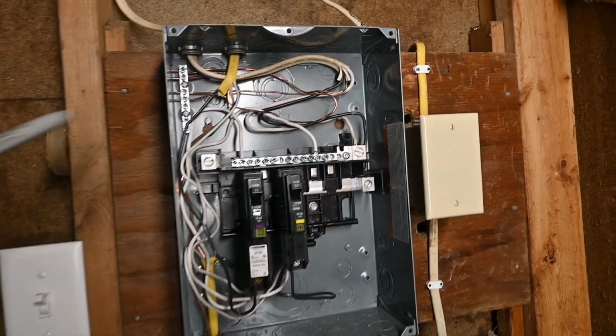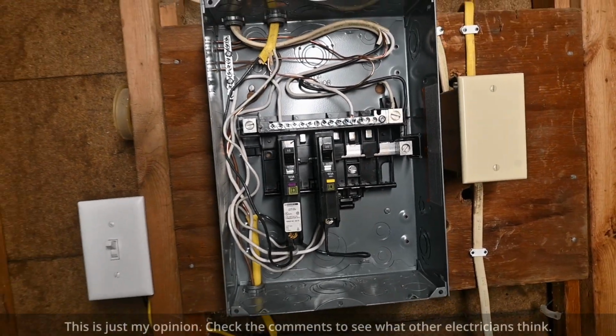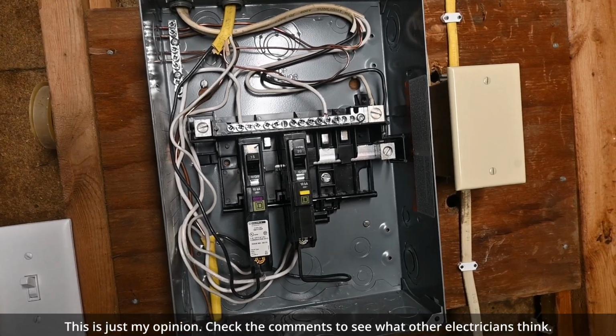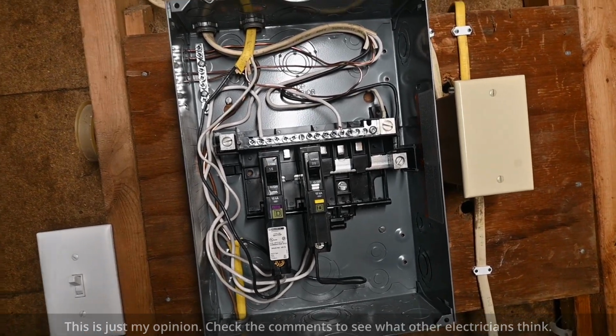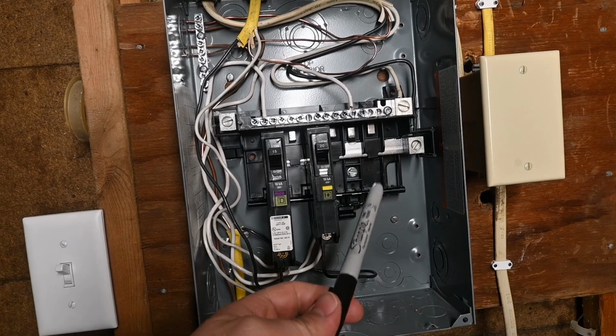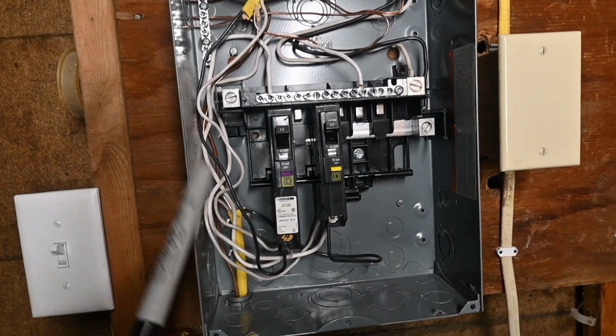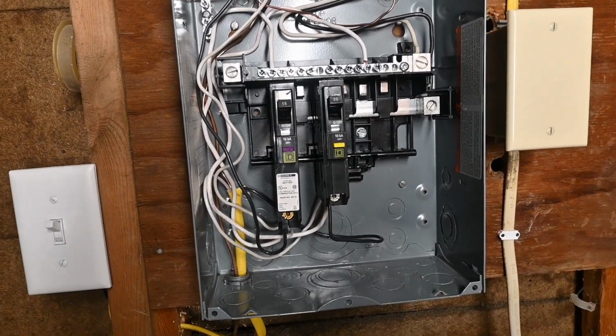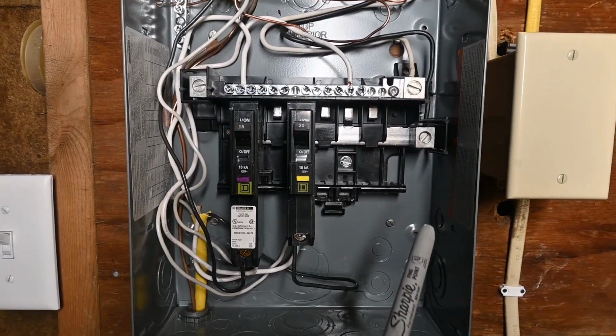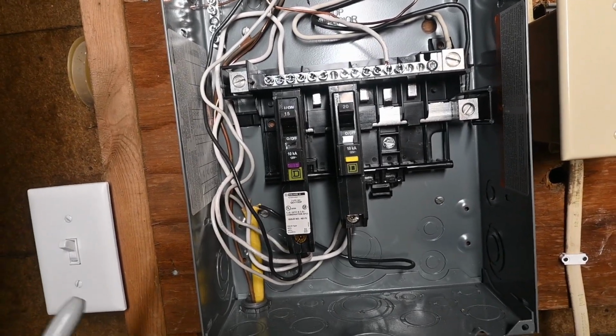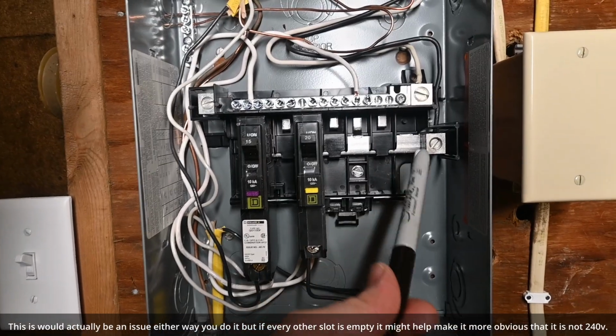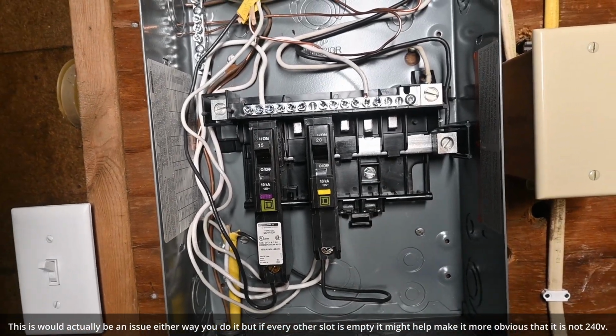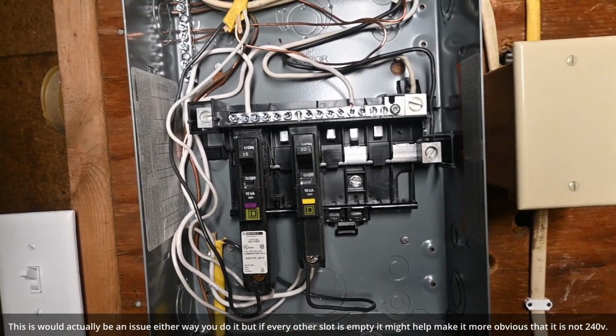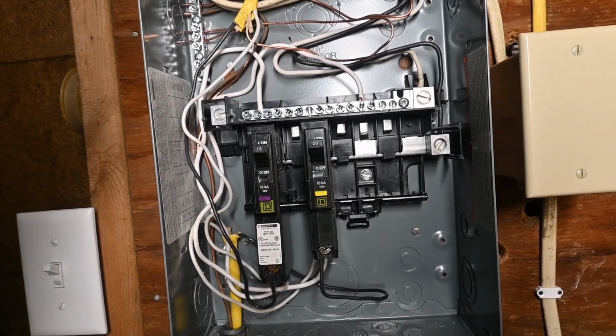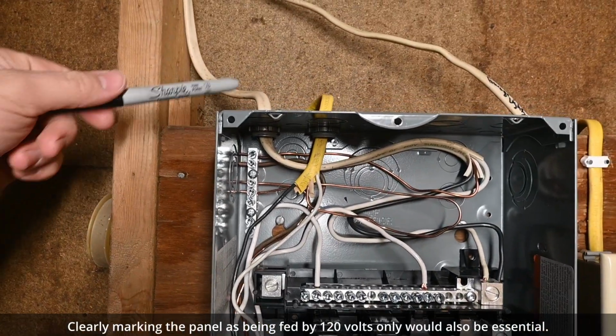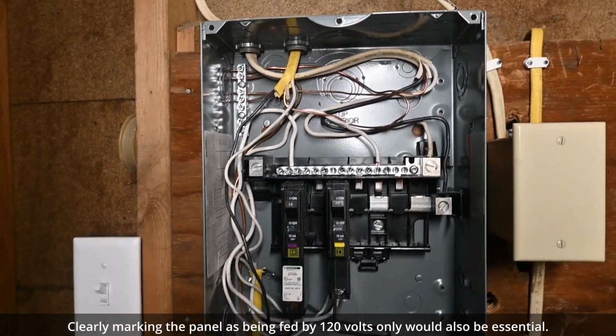Now, I do not recommend doing that because it is unclear what is going on when you are looking at a panel. Every other slot should be coming from every other leg of 240 volts. By leaving just one connected, that's going to make somebody think that, oh hey, there's two slots available right here, I can pull 240 volts out of this panel. If they were to try doing that, they would discover that one of the legs is dead, and then they would realize, oh, this is just being fed by 120 volts.